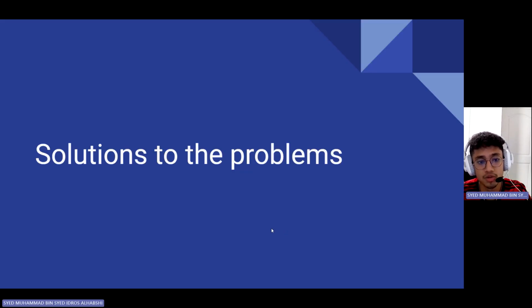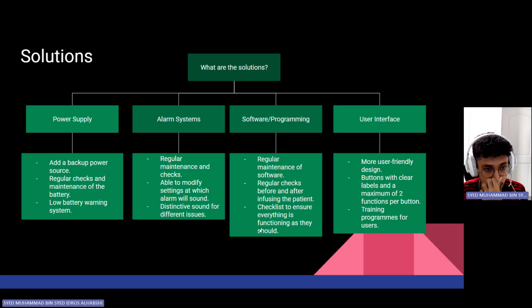So, what are the recommended solutions? As for the power supply, a backup power source should be added so that in case the first power source melts or has a problem, the backup power source can help continue to run the infusion pump so that the patient can continue being administered the liquid they need. There should also be regular checks and maintenance of the battery to ensure that the battery is not faulty right before an infusion. And if there is a faulty battery right before the infusion, users can actually change the battery before starting the infusion to reduce the chances of an incident happening or any complications.